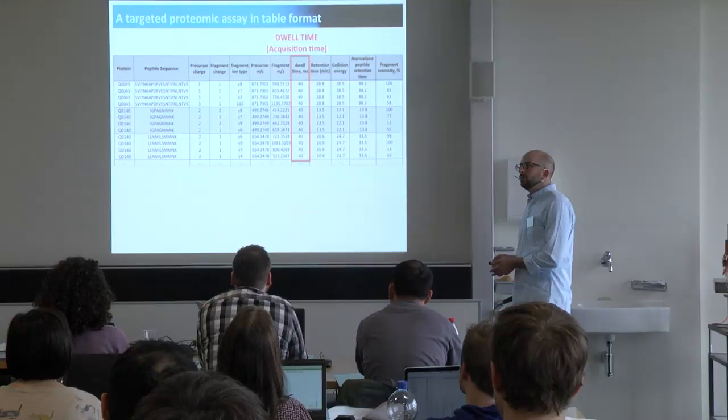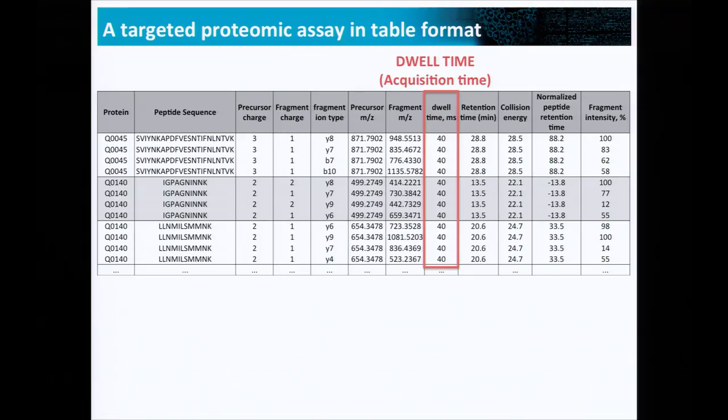The next point that I would like to talk about is dwell time. Does anybody have questions until now about collision energy? No. So dwell time is basically what we tell the machine: how long do you want to spend measuring a certain transition in this case. This relates to sensitivity.